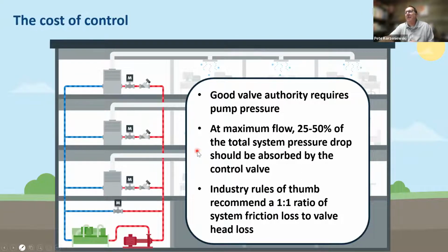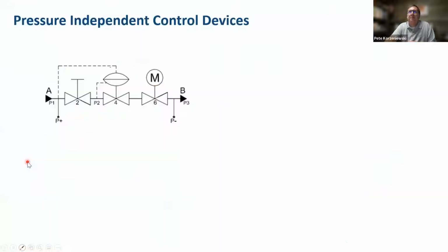If we, for example, need 70 or 75 feet of head to overcome the friction loss for our design flow through our hydronic system, our chill water system, we've got to basically add another 75 feet of pressure loss for that valve to have the proper authority. And as you dig into different industry, different manufacturers' manuals on sizing and selection, the rule of thumb that I've been able to come up with and that seems common is a 1-to-1 ratio of system friction loss to valve head loss. So it's just a different way to say the same thing. But that is a huge amount of head required for these valves to operate properly.